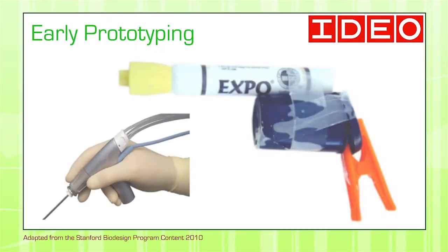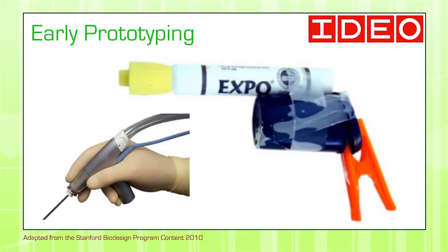So there was a need statement: how to make this more usable, or easier to use, or how to make the surgeon more agile using this type of electrosurgery tool. That was on the table, and of course the design constraints surrounding that problem. With that in mind, the brainstorming session started. And something truly impressive is that one of the very early prototypes made during these first brainstorming sessions actually became the basis of how the product finally looked.